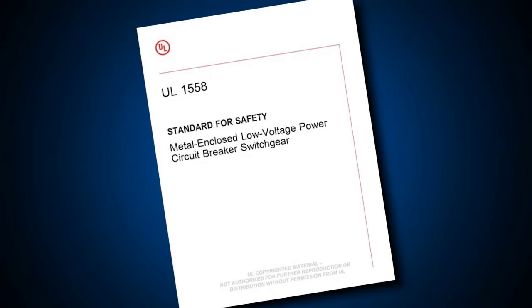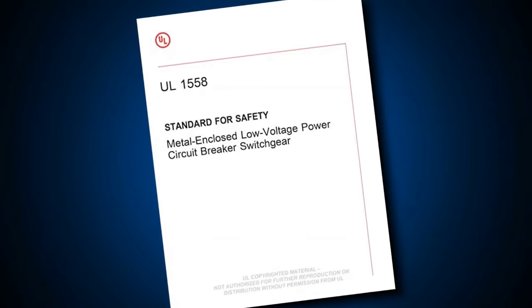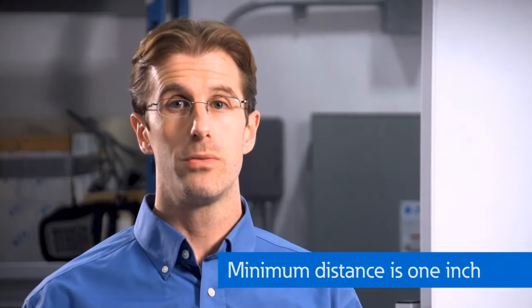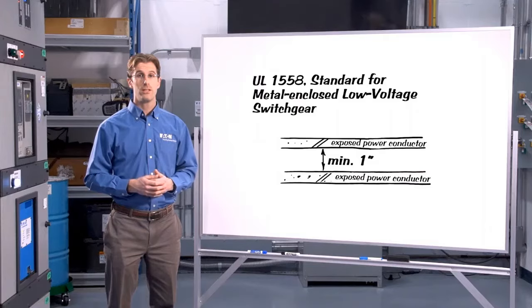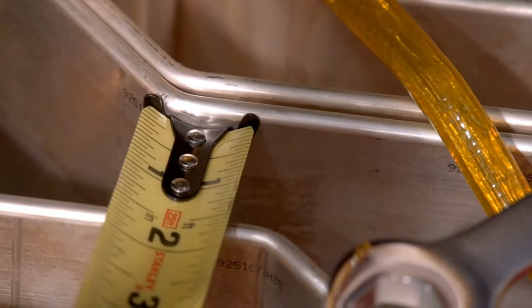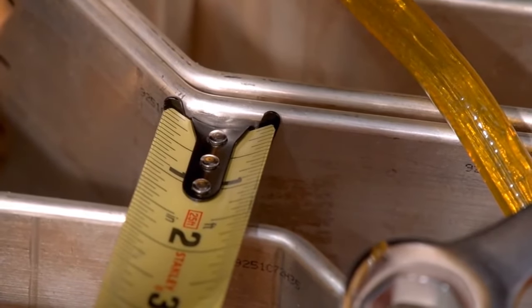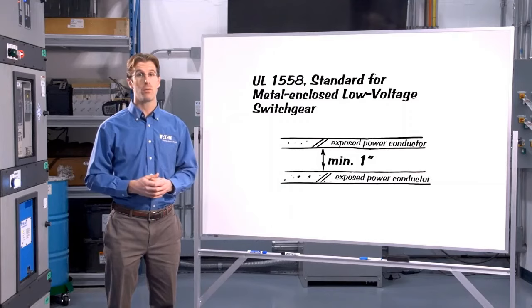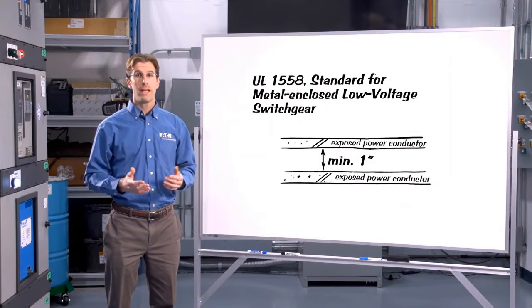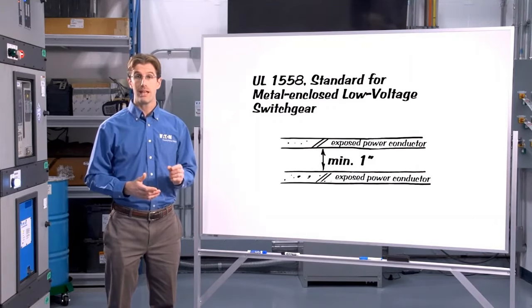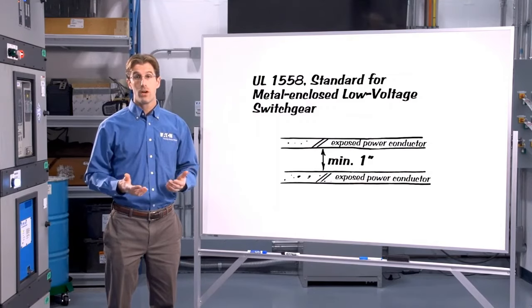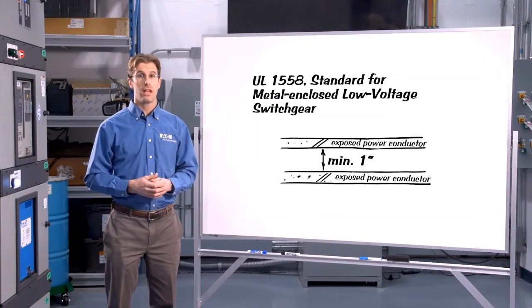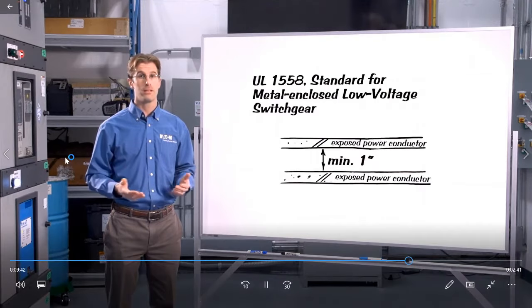First of all, UL 1558, which is a UL standard for metal enclosed low voltage switchgear, states that the minimum distance between exposed power conductors is 1 inch. So that means inside our switchgear, all of the uninsulated bus bar and other power conductors are at least 1 inch apart, and in most cases far more than 1 inch apart. So by making the contacts inside the arc containment vessels less than 1 inch apart, when we create an arcing fault across them, the laws of physics guarantee that the arcing fault will be lower impedance than any arcing fault that could occur across exposed power conductors inside the switchgear.